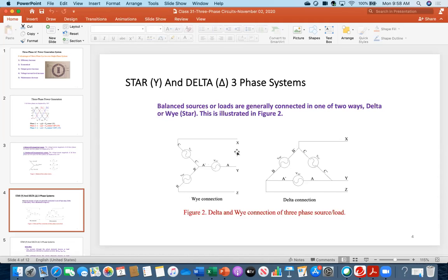What conclusion will you get? Line to line voltage will be a combination of two branches, root 3. It will be root 3 times of this voltage. Everybody see? For example, here you got 120 volt. So here you will be getting root 3 times of that. So I think you will be getting 208 volt. Can you calculate? 120 multiplied by root 3. How much are you getting?